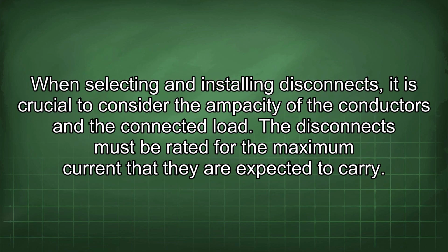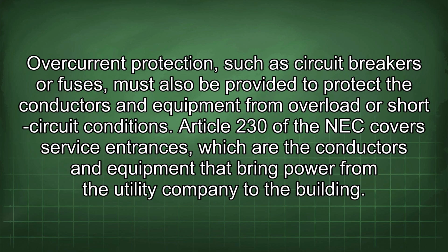When selecting and installing disconnects, it is crucial to consider the ampacity of the conductors and the connected load. The disconnects must be rated for the maximum current that they are expected to carry. Overcurrent protection, such as circuit breakers or fuses, must also be provided to protect the conductors and equipment from overload or short-circuit conditions.